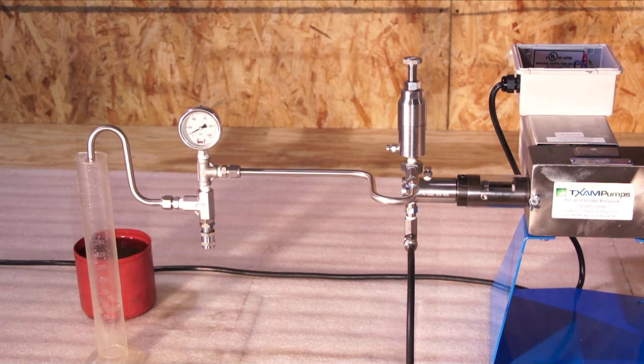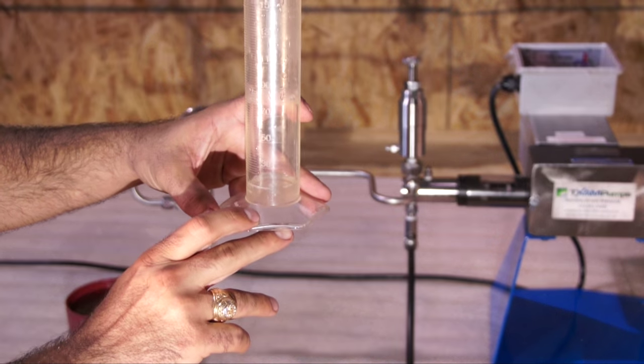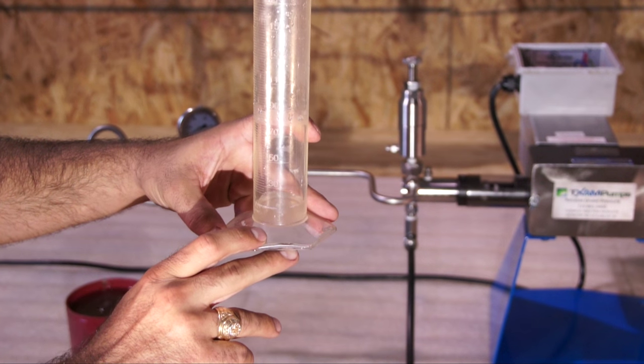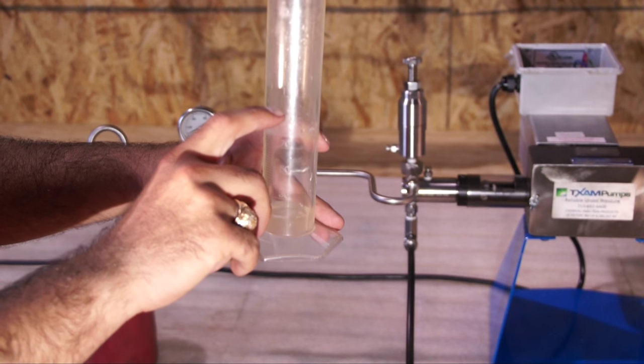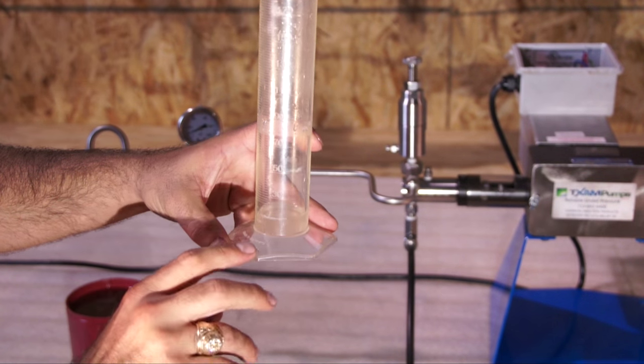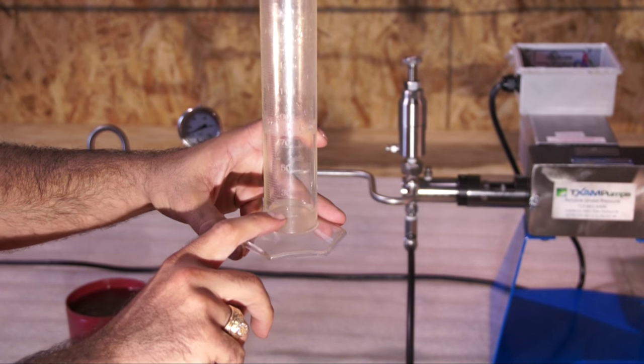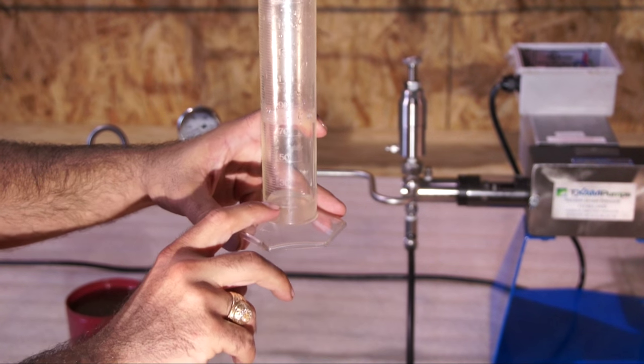Now I'm going to demonstrate the lowest possible setting for the flow control valve itself. Rather than 95 to 100 milliliters per minute, we only receive 26 to 28 milliliters per minute.